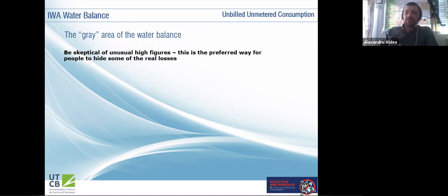The problem is that when you compare the burst records, when you compare the figure for the real losses, and this has happened to me so many times, there are situations when the volume reported as the real losses is much smaller than the volume reported as unbilled consumption. So this is a component that requires special attention.